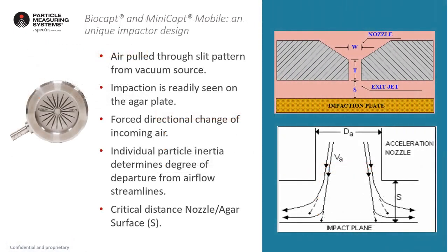The design of our impactor is unique on the market. As you can see from the image, it has 20 slits that form a radial design. This design is clearly visible on the agar after sampling, and the peculiarity is that it allows the operator to immediately evaluate the quality of the sample. The design of the slits ensures the correct direction that impacts the surface of the plate. We can say that the microorganisms are gently placed on the agar, ensuring their survival — that is the goal of the sampling. Last but not least, the distance between the agar and the impactor is always constant. All those parameters ensure the correct and best biological efficiency of an active air sampling.